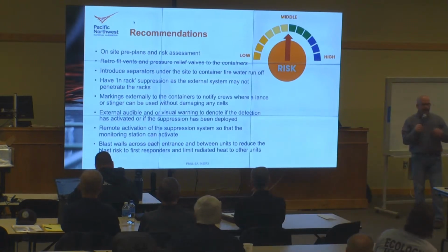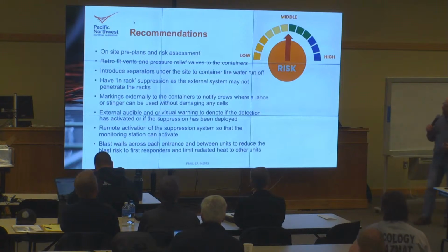All right, what did I say? What was my opinion about pressure relief valves? Matt's not a big fan of them. Let's use deflagration prevention—let's not let the gases build up, right? If they want to do that on the top as well, that's fine. Have in-rack suppression, as the external system may not penetrate the racks.